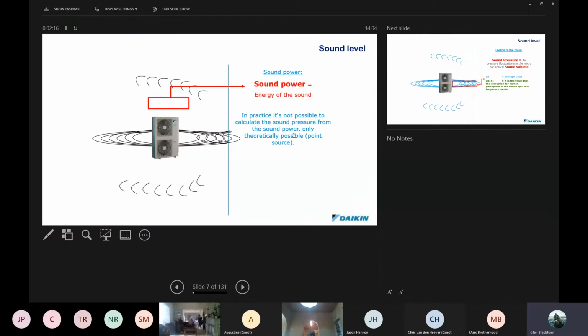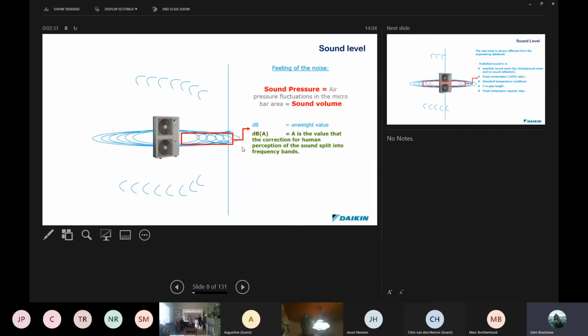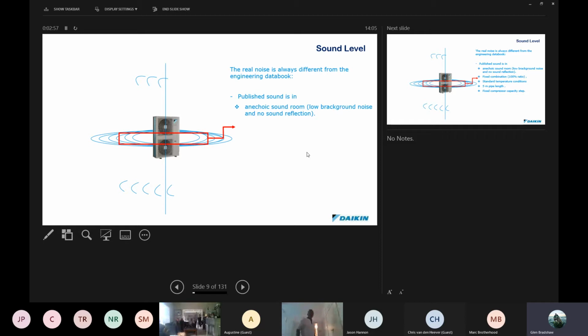Sound power is the energy of sound. Okay, in practice, it's not possible to calculate the sound pressure from the sound power. It's only theoretically possible from a point source. I'm going to just build that up slowly. The feeling of noise or sound pressure, air pressure fluctuations in the microbar area. So the way we perceive sound in our ears is by pressure, as that sound fluctuates. Okay, and that's the volume. And then it's measured in the decibel weighting, and the dBA is the value that is the correction for human perception of sound split into frequency bands.